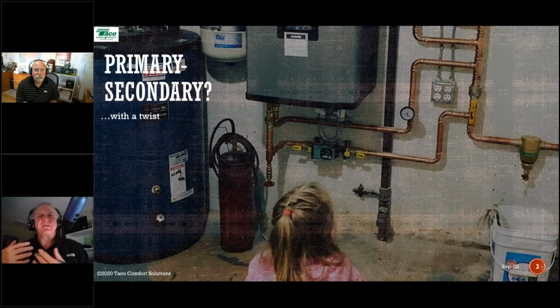When we do primary, secondary piping with a cast iron boiler, all right, we make a connection. There's the supply port up on top and the return port back on the bottom, and we simply connect those with a big hunk of pipe, and we take secondary heat deliveries off of that primary loop. The primary loop is the big pipe, and then we have secondaries coming off of that with our T's, 6 inches or 4 pipe diameters apart for our different delivery units.